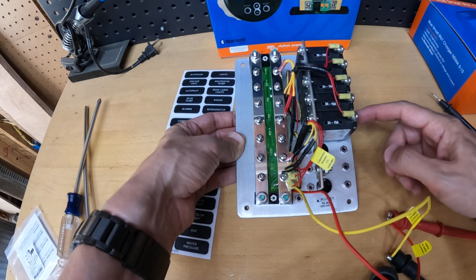I've got a nice DC bus, and then I also have a DC ground bus, which isn't really a concern on my little sailboat with an outboard motor. But if you have an inboard motor with a metal shaft that is grounded, you can run into concerns with stray currents eating up metals and sacrificial zincs. So I'm not going to cover that here, but that's the purpose of your second bus there — it's for the DC actual earth ground, or the water ground system.